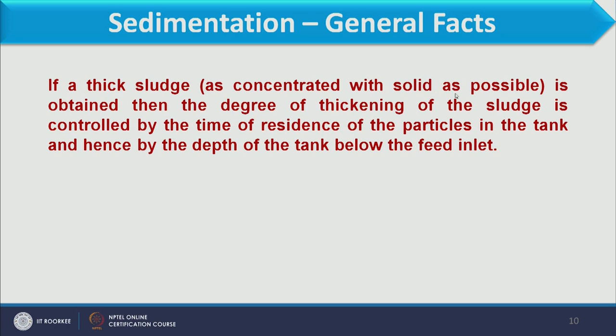If a thick sludge as concentrated with solids as possible is desired, the degree of thickening is controlled by the residence time of particles in the tank, and hence by the depth of the tank below the feed inlet. So for obtaining clarified liquid, diameter is the main concern, while for thick sludge production, height is the main concern of the thickener. These are the two key design factors.